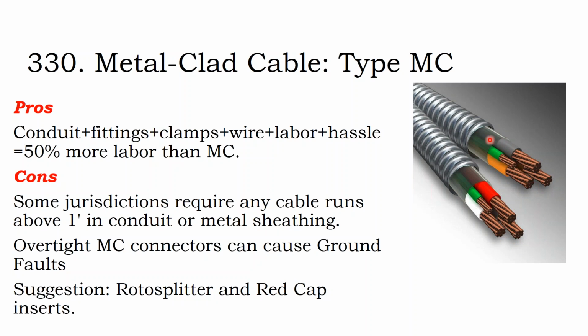It might be that you can use this ground for your equipment ground conductor, but you have to run a separate DC grounding electrode conductor up to the roof, independent of this, because it might need to be a larger size. If this is number 10, then often this cable might be number 8. Or sorry, this cable might be number 12, and that wouldn't meet the smallest size. That would be too small for your smallest equipment ground conductor for a solar array. So you sometimes need to run your grounding separately, and where you do run an equipment ground conductor separate from the rest of your array conductors, it still needs to be run with your wires.